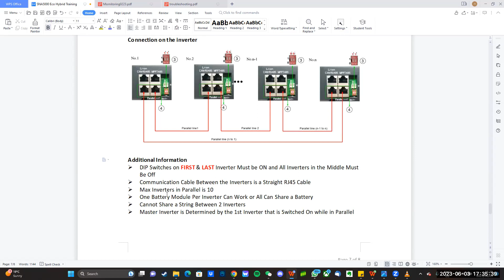In a parallel setup, if you have more than one battery, we recommend paralleling the batteries together. On the master battery, depending on the battery type you're using, take the positive and negative from the appropriate terminal points, feed that through a bus bar, and split that into all inverters. Then on the setting side, program the setting as battery shared. This is what we recommend, so if one inverter goes down, it's still connected to the other inverters.